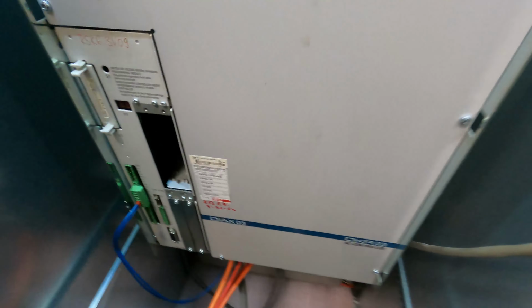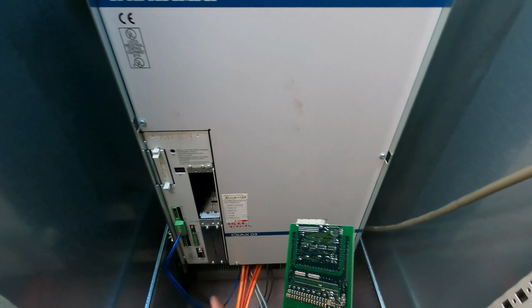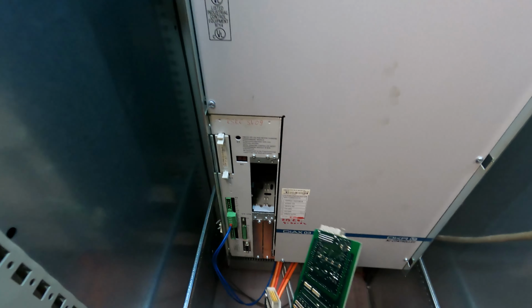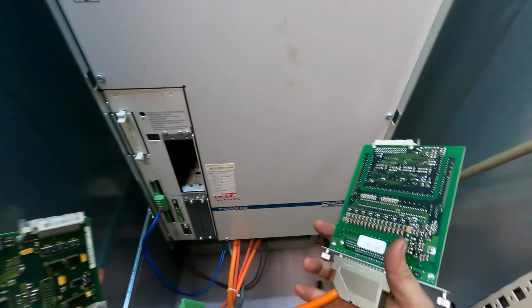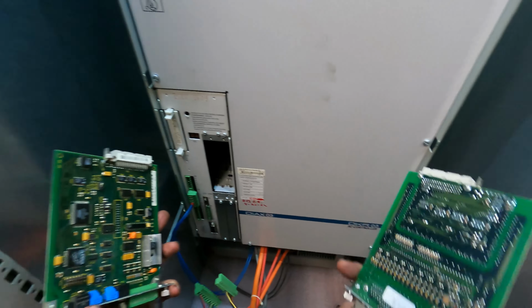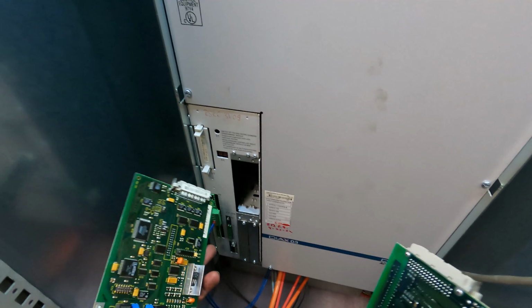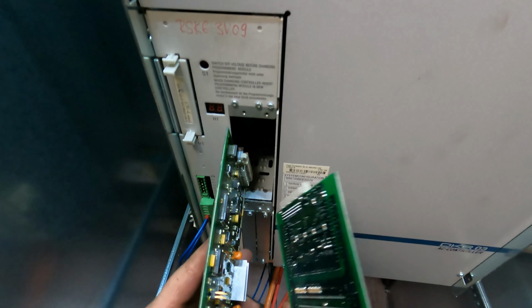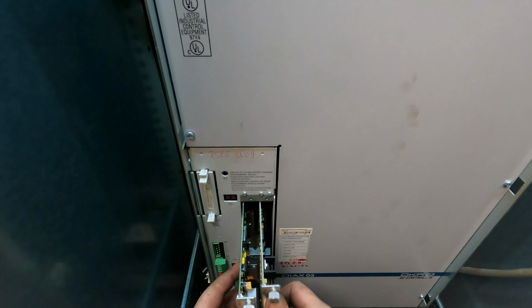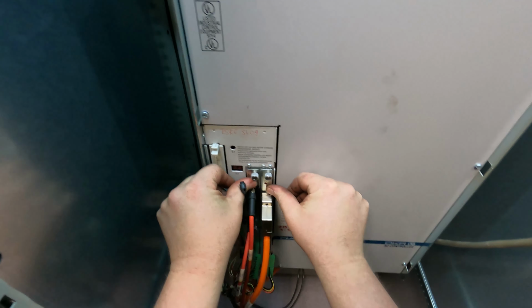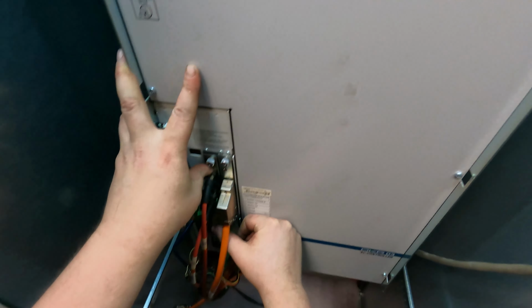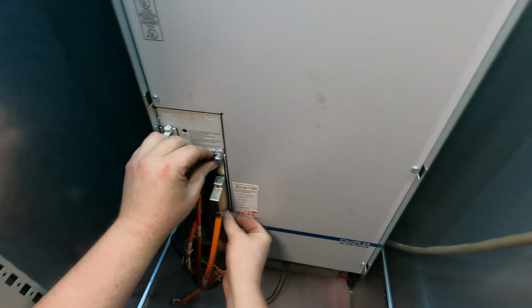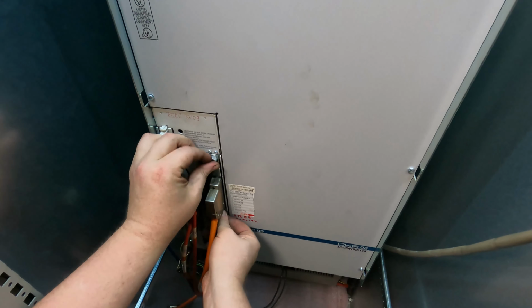And then the only other one that you could mess up is you could put the wrong card in the wrong side right here. But if you just remember, the big orange one goes on the right, the two little red ones, the fiber optic card, goes on the left. And you want to make sure that these cards line up with those grooves in there. Okay. And then just push it in. And that seats it.